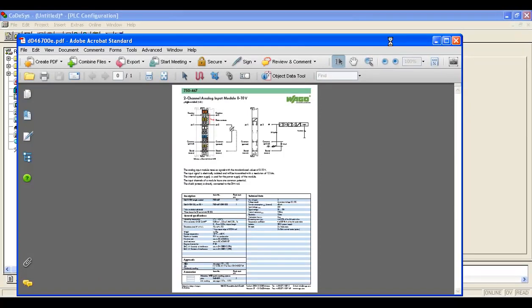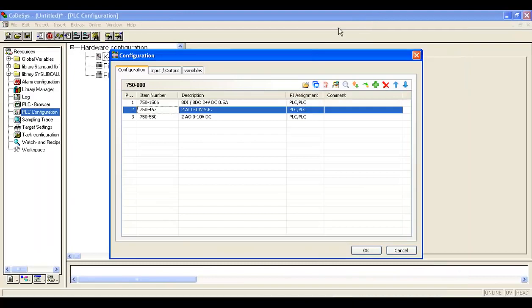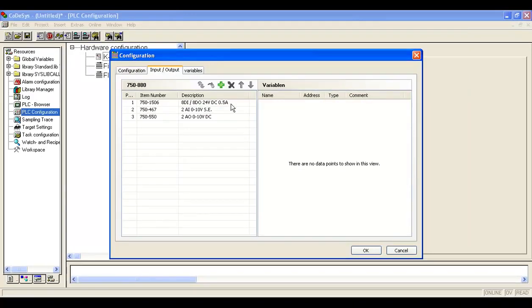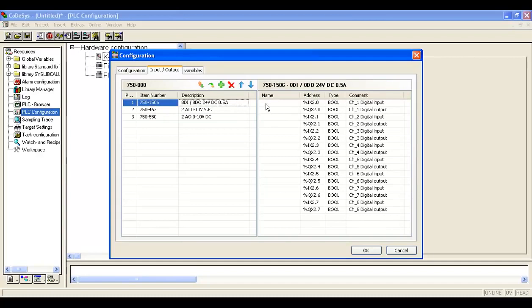Okay. So another thing that you can do, of course, while you're in here is point your variable names to the hardware addresses themselves. In here, I'm just going to put some very simple input and output variable names. You want to be a little careful here when you're using the 8 in, 8 out card, because if you notice, the input-output structure here is alternating. They're not grouped, with inputs and outputs separated from one another. Again, they're alternating. So I'm just going to put in a couple variable names here for this project.